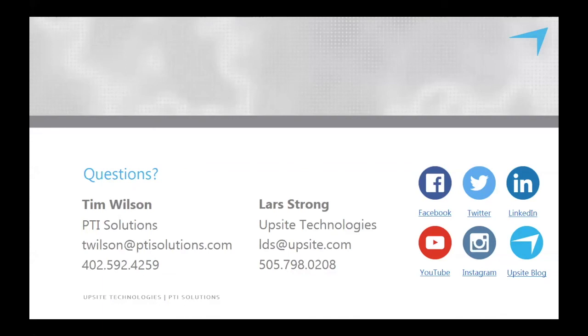What is the battery life of the EkkoSense sensors? The sensors are set at a 2-minute polling, which is fairly frequent. We guarantee 3 years and typically get as much as 5 years of battery life out of them. They do have indicators to note when their batteries are getting low, and they can easily be field replaceable by the end user.